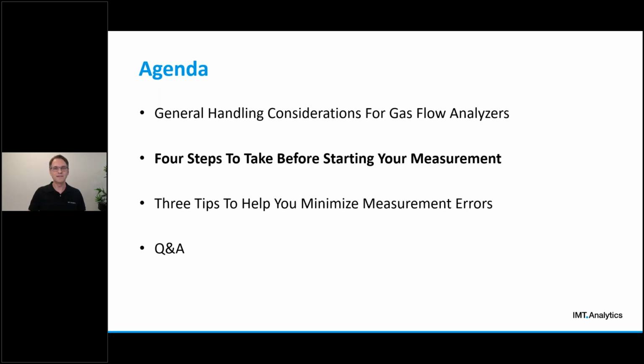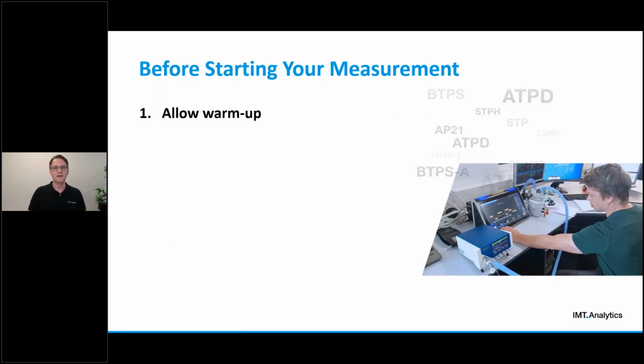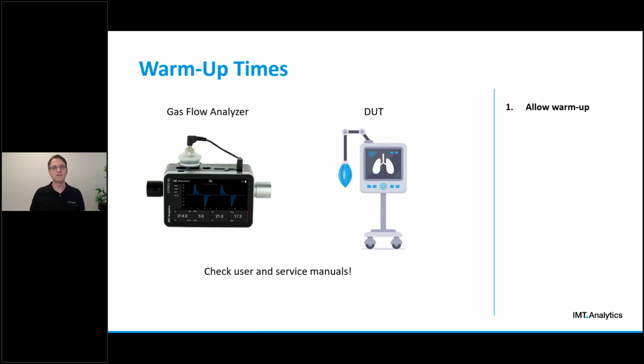So the first point is to allow warm-up. This is to avoid taking measurements while the sensors of the devices are still undergoing some warm-up related temperature drifts. It's important that your gas flow analyzer, but also your device under test, are both warmed up before you start taking measurements. Warm-up times of analyzers and ventilators can vary by device. So in most cases, the manufacturer specifies the required warm-up period in the user or the service manual of the device. If you can't find such information, a good practice value would be 30 minutes. Then I'm pretty sure you're on the safe side.